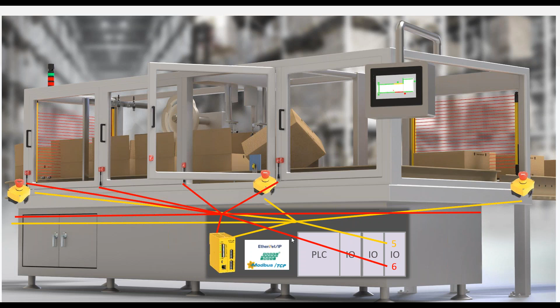We do that with Banner's in-series diagnostics. And what that means is we have devices that can communicate with the SC10. They're connected with simple 4-wire cables, T connectors, back directly to the SC10. Now in the 4 wires that are in this cable, 2 of them are for power, so they go over to the power supply, and the other 2 hook up to the SC10. You can have up to 32 devices connected together in this manner, where you have T connectors and 4-pin cables all the way around the machine.